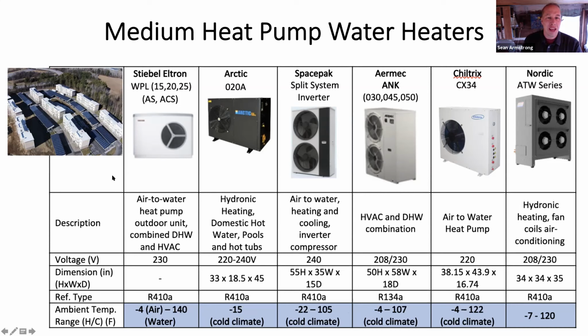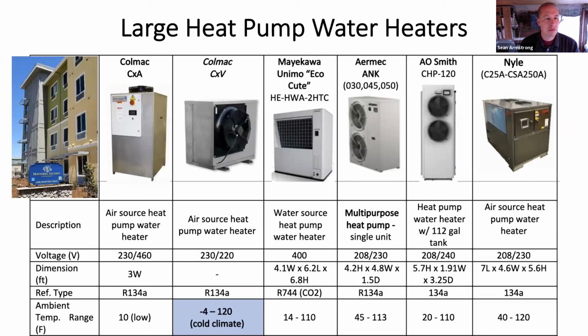These units have refrigerant inside. It's released hot, goes to a storage tank, and comes back cold to get reheated. This sits outside of a building. These are air-to-water heat pumps and can handle anywhere from 9 to 20 apartments, one of these 3-ton products. So they're really right-sized for a building or a campus.